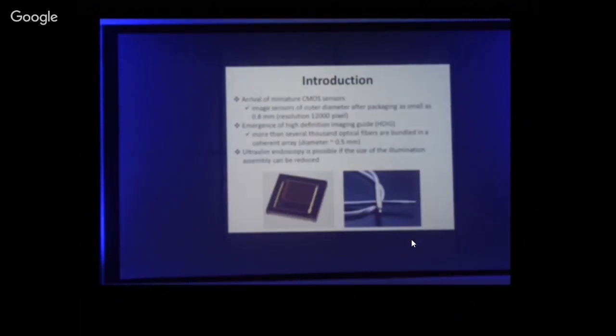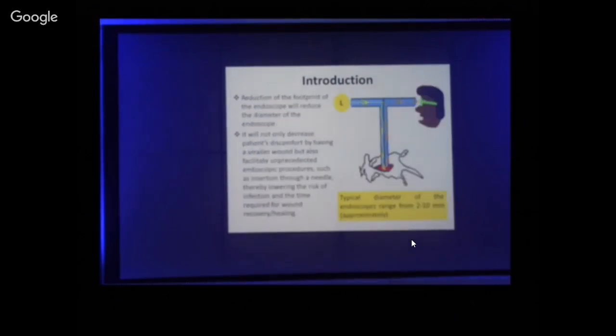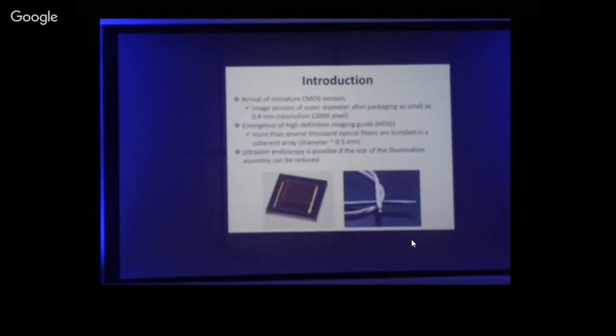Fortunately, nowadays there are many CMOS sensors on the detection side. As I said, the detection part consists of the collection fiber and the image sensor. There are now CMOS image sensors as small as 0.8 millimeter, with a resolution of 12,000 pixels. And we have high definition image guides, where more than 10,000 optical fibers are bundled in a coherent way in a diameter of around 0.5 millimeter. So from the detection part, it is okay. We can reduce the diameter of the endoscope.